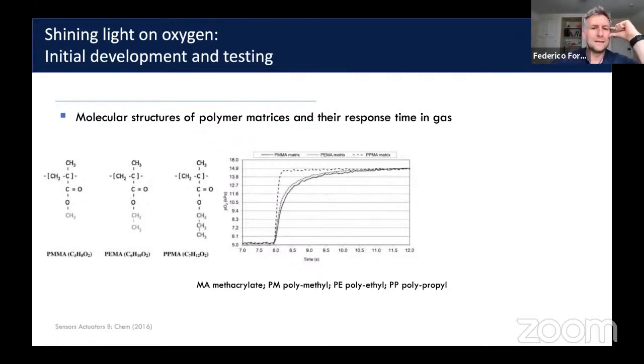And the key point of the rationale here: we see some of the polymer matrices that Rongsheng tested and the associated response time in the graph over here on the right, where you see that the 3 different matrices had different response times. In this example, the PPMA matrix had the fastest response time, in response to a square wave change from 5 to 15 kilopascals in terms of the partial pressure of oxygen. You see that the vast majority of that change was detected within a fraction of a second. Here we have time in seconds from 8 to 9 seconds.